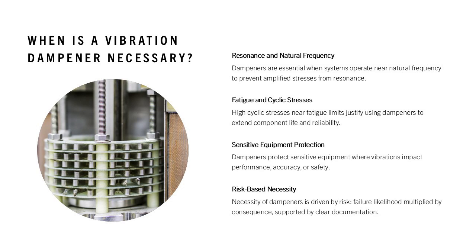Regulatory requirements, industry standards, or manufacturer specifications may explicitly mandate vibration control. Importantly, necessity is defined by risk, the likelihood of failure multiplied by consequence. Engineers should document these conditions clearly when recommending dampeners to ensure defensible and traceable design decisions.